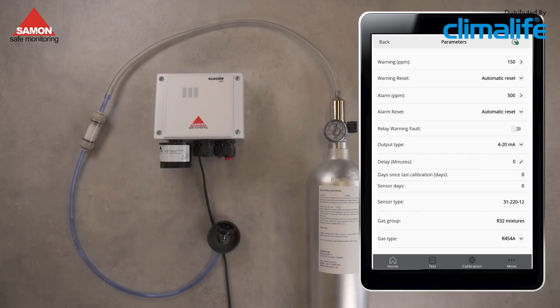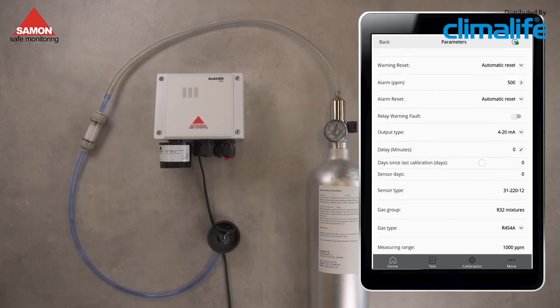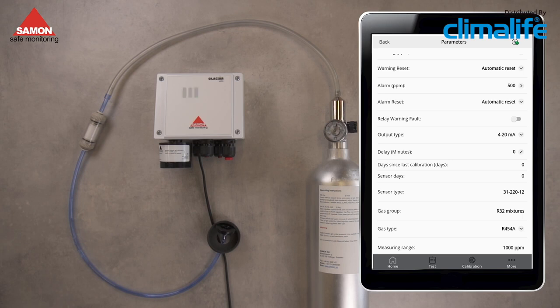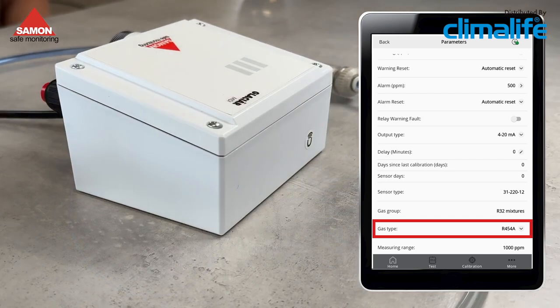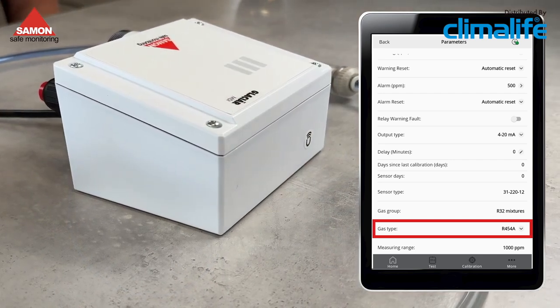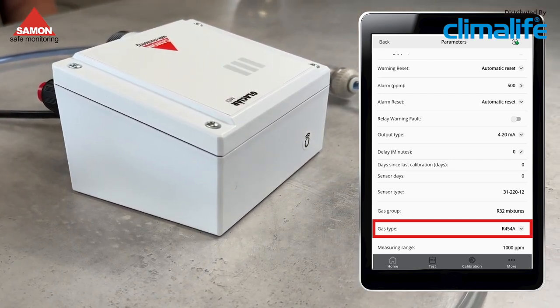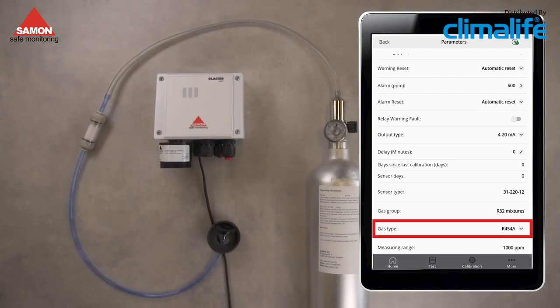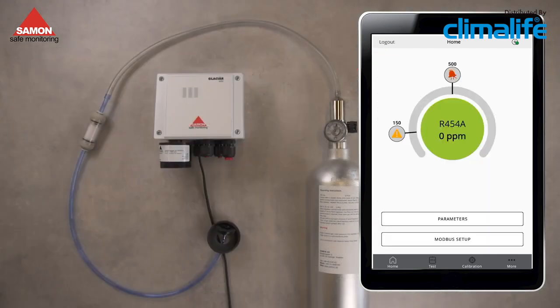To confirm which gas type the Glacier MIDI is configured to detect, navigate to the Parameters menu. Scroll down to Gas Type. You will see that the unit is set to monitor R454A. It is not necessary to change the gas type to match the calibration gas. Simply keep the current setting for the gas the detector is intended to measure. The Glacier MIDI will automatically recognize and adjust for the calibration gas during the process. Click Back. Now you choose Calibration from the footer menu in the app.